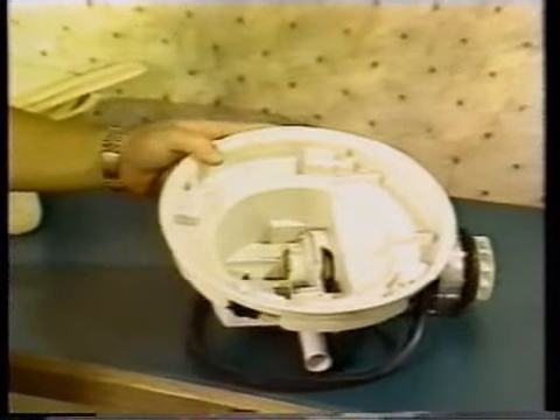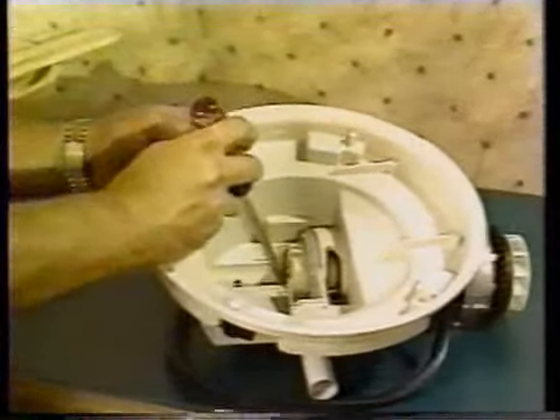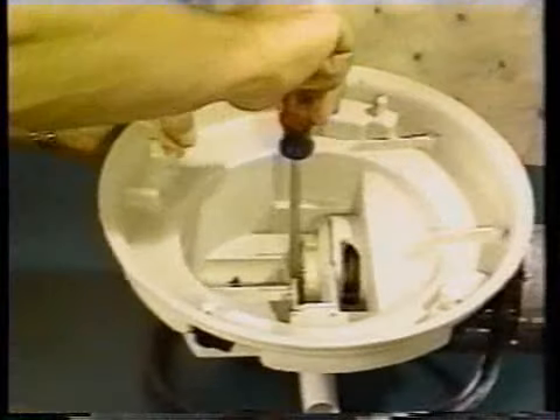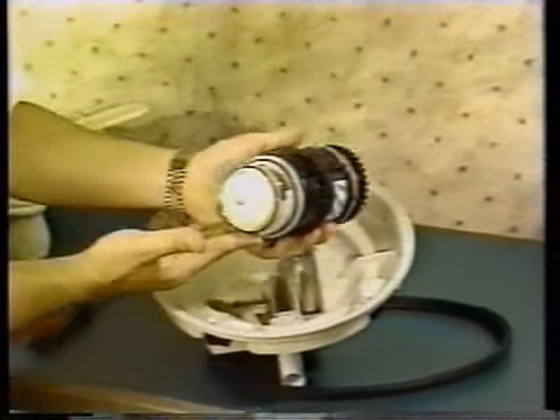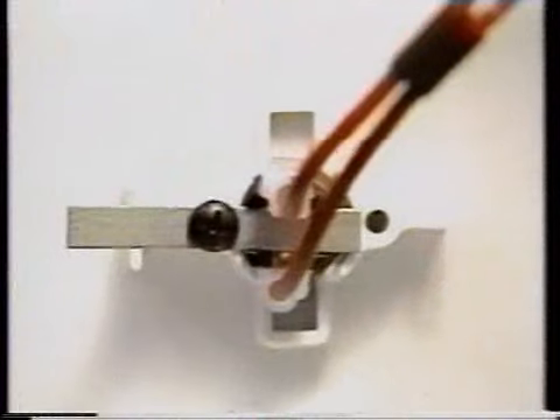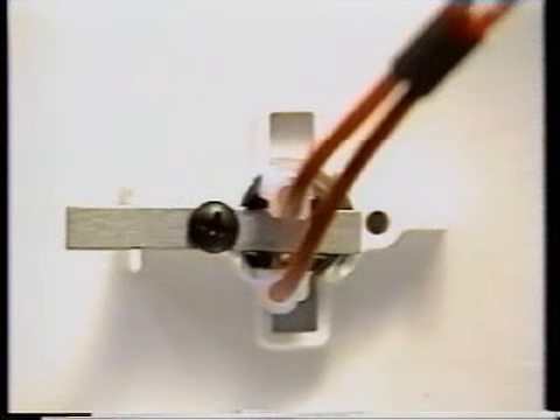With it removed, place a large screwdriver between the housing and the impeller. Force the impeller and motor out of the housing. Do not try to remove them by pulling on the motor or rocking the motor. To remove either the Temp Assure or Temp Boost thermostat, after disconnecting the wiring, remove the screw holding the thermostat in place. To remove the safety thermostat, simply unscrew it from its mount.